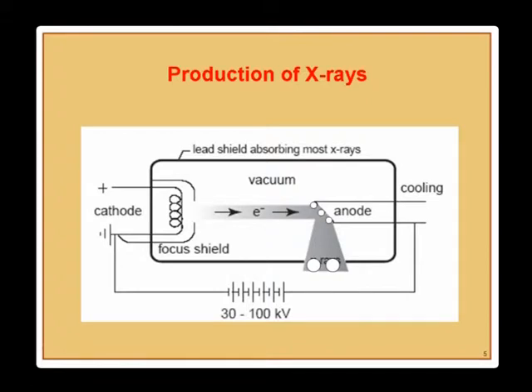Electrons impinge on the anode, creating x-rays. Typically only two percent of the energy impinging on the anode is used to create x-rays; the rest goes away as heat. It's a very inefficient process. The anode is also cooled, typically with an oil cooler. X-ray tube manufacturing is a specialized area with just a few companies making them. In computed tomography, currents can be as high as 2000 milliamps, but in a standard chest x-ray it's just tens or maybe 100 milliamps maximum.